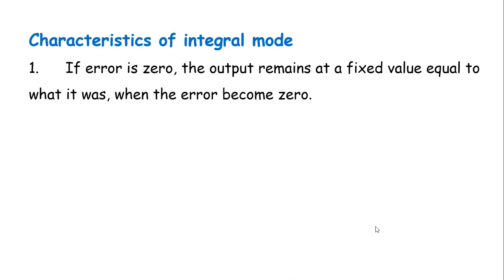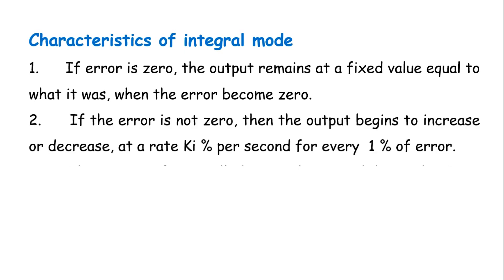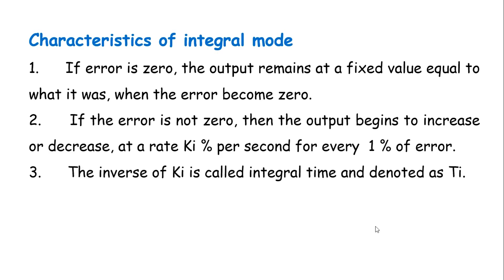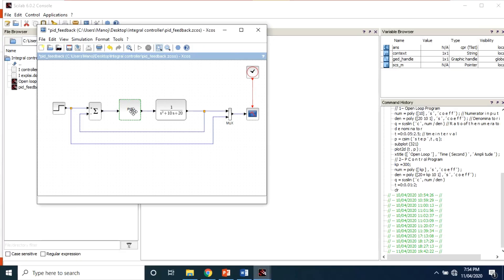Summarizing the characteristics of integral mode: first, if the error is zero, the output stays fixed at the value it was when the error went to zero. Second, if the error is not zero, the output will begin to increase or decrease at a rate of Ki percent per second for every 1% of error.